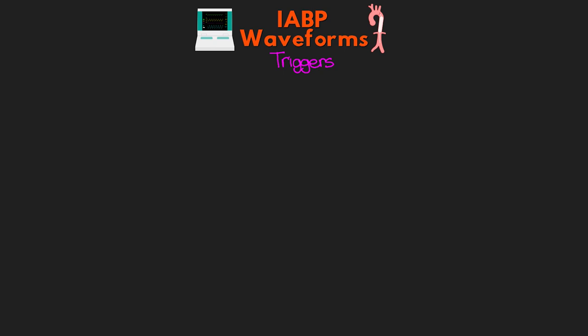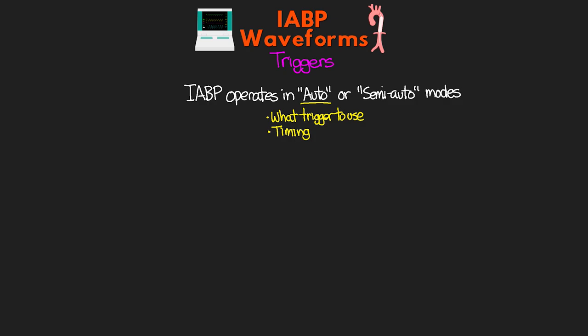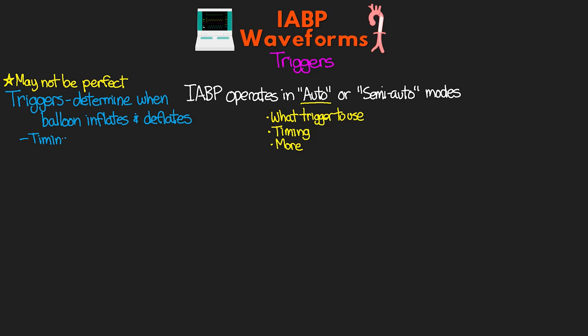The balloon pump can operate in either auto or semi-auto mode. Typically we keep it in auto mode, but there are times where we need to optimize the operation of the balloon pump itself. In some places you may not be able to place it in semi-auto mode and fine tune things, so make sure you know your facility policy. In auto mode, the balloon pump is going to determine on its own the best way to run — what trigger to use, adjust timing, and other things. It usually does a pretty good job. The triggers are what actually determine when our balloon inflates and deflates. The timing of inflation and deflation in relation to the trigger may need to be adjusted, though in auto mode the balloon pump automatically makes these adjustments.